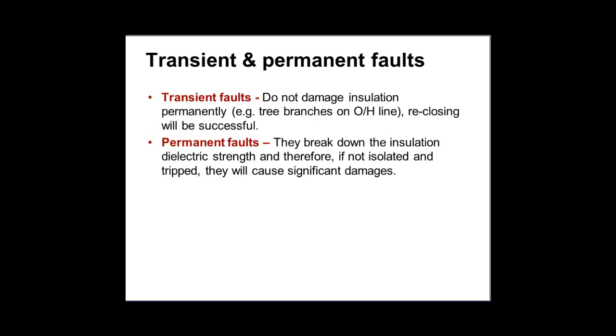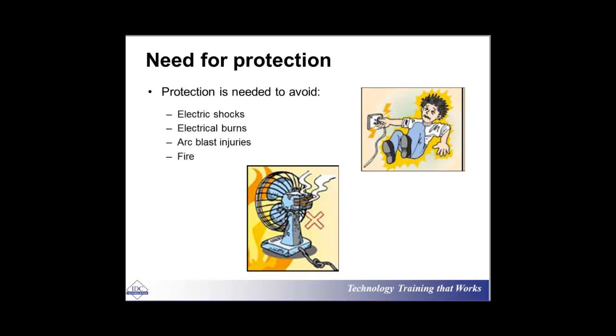So a recloser is a kind of circuit breaker that, as soon as you have a fault, will open. Like a timer, it will wait 1 second, 2 seconds, 3 seconds, and then close again. That's why we call it the recloser, just to make sure that the fault has gone. If the fault is still there, it opens again, counts down 1 second, 2 seconds, 3 seconds, and closes again. If it's a three-shot recloser and the fault is still there after the last attempt, it's not a transient fault. It's a permanent fault, and it will lock out and stay permanently open. So these are the things.